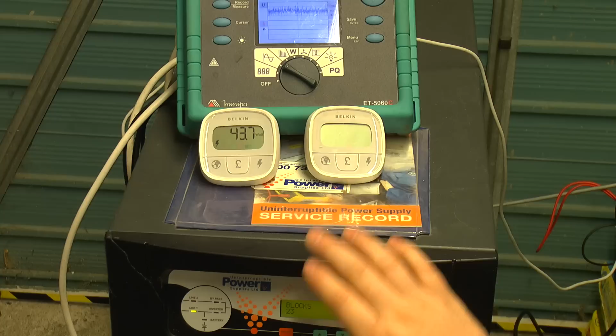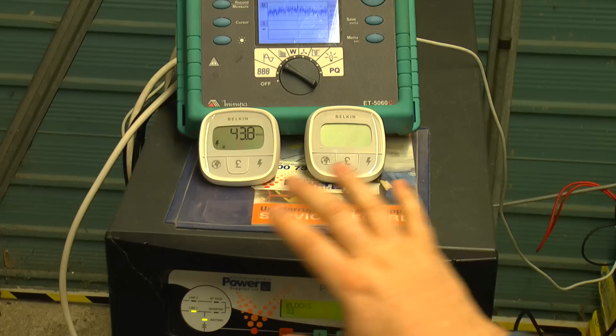And if I go into the service menu now, I can change the battery type, and change the overall autonomy and number of battery blocks. Now it says 23, the unit takes 46. That's because it's got two separate sets of batteries. It's got a negative, then 23 blocks later you've got the center connection, and then another 23 to the top. And the manual says it can handle between 30 and 50. So that would be between 15 and 25 on here. And it's currently set for 23.